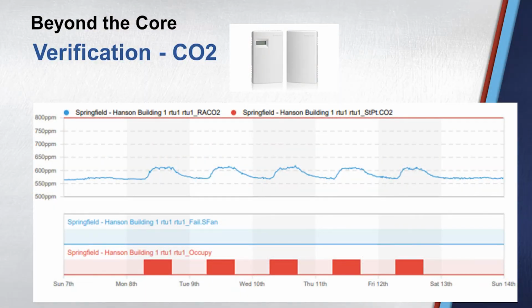This is just using a CO2 sensor, which you shouldn't blow directly on because it invalidates the reading. But in essence you can use that reading along with PM 2.5, join it all together, and start controlling your systems to be predictive about what you're doing, as opposed to just assuming I've got my right outside air, I've got my filter, and I'm good.